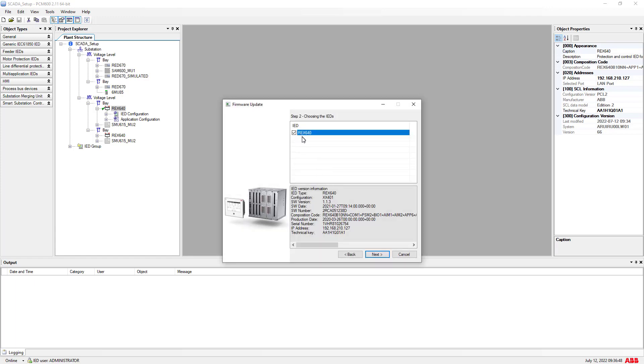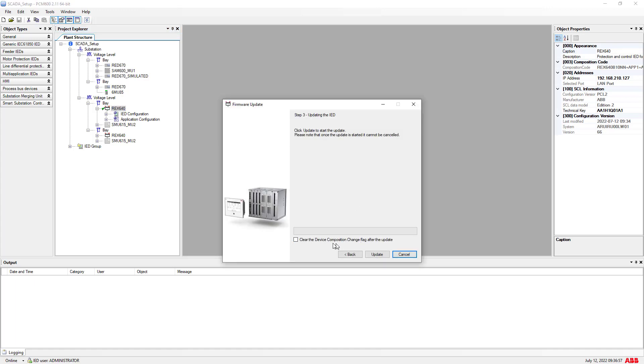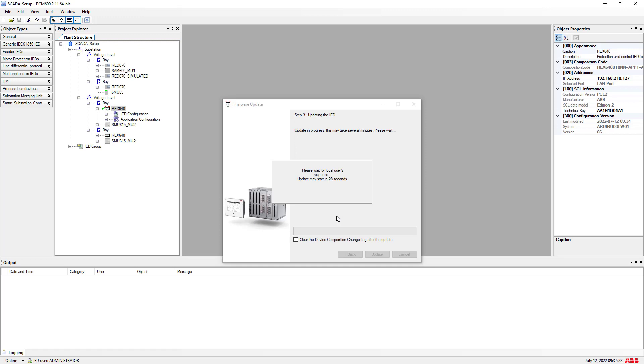Go next — this is the selected IED — and proceed further by clicking next. You can also enable the option to clear the device composition change flag, then continue with the default selection by clicking update. At this point, the local user also gets an option: from the LHMI of the REX640, an approval will be required. You can select Allow so that the remote update proceeds quickly; otherwise, it will automatically proceed with the update.